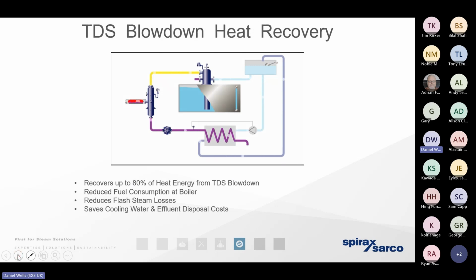Now, we can't recover any of the heat energy from the bottom blowdown because best practice says that that needs to go straight to the blowdown vessel itself. But with the TDS blowdown, we can. This has got a very attractive payback. It's something that's quite often overlooked because in years gone by, when the energy centre was engineered, the cost of gas, the cost of steam was relatively low. Carbon emissions were misunderstood. Whereas today, we know that if we're able to recover as much of the heat energy from the water that's leaving the boiler and put it into another process, such as the hot well, then we appreciate the beneficial effect that can have in reducing the mass of steam that the boiler needs to produce, and therefore help us to reduce our cost of gas and reduce those carbon emissions.